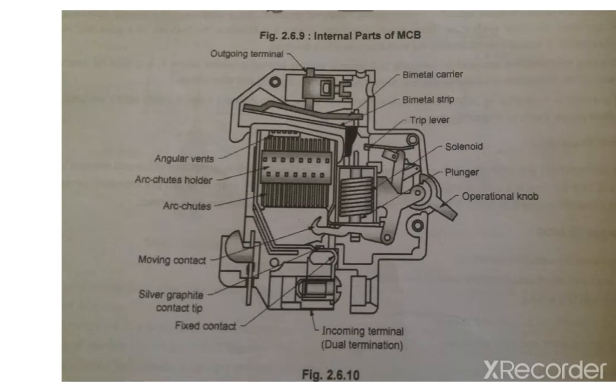As this large amount of current is flowing through this solenoid coil, a large amount of flux is produced in the plunger. Due to this, the contact opens. The fixed contact and moving contact are designed in such a way that the arc which is produced between them moves towards these arc splitters, and due to this, lengthening of the arc takes place and the arc is extinguished. The closing of the MCB is done manually only by operating this operating knob. The rating of the MCB is decided according to the phases, as single phase or 3 phase, and it is defined from 0.5 ampere to 63 amperes. This is it for the miniature circuit breaker.